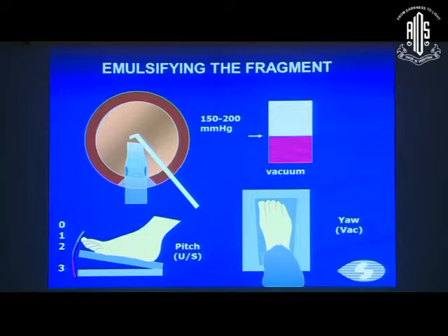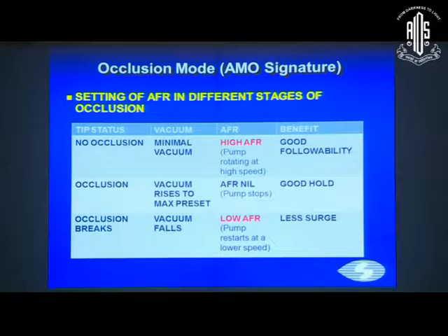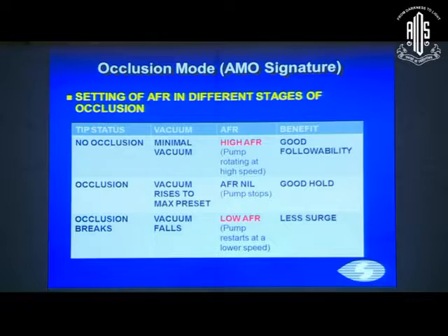In the pitch, the ultrasound can be increased or decreased as necessary. The occlusion mode for phaco is present in the AMO Signature. When the tip is not occluded, there is minimum vacuum and a high aspiration flow rate, with the pump rotating at high speed for good followability of the fragment.